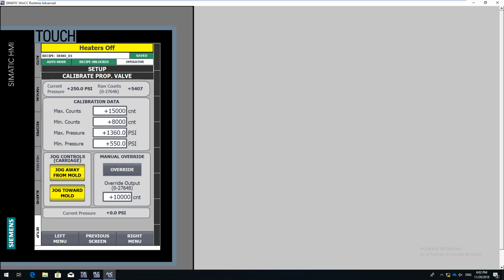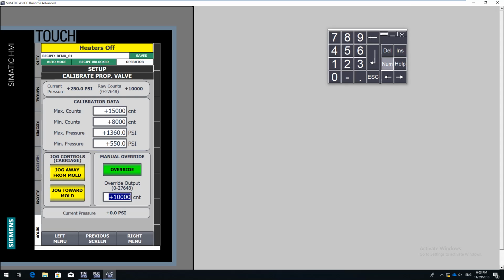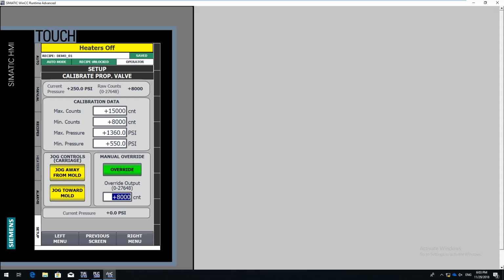Now, dialing in the calibration data, again, we shouldn't be changing this too often, but you might have to tweak it a little bit. And this involves, again, what's our minimum and maximum counts, and then seeing what the pressure is. So what we do here is, instead of jogging the axis up and down and seeing what the pressure is, I will manually override the system. For example, I will type in 8,000 counts, and I'll drive the carriage up. And then I will look at the pressure gauge on the machine and see what I read.